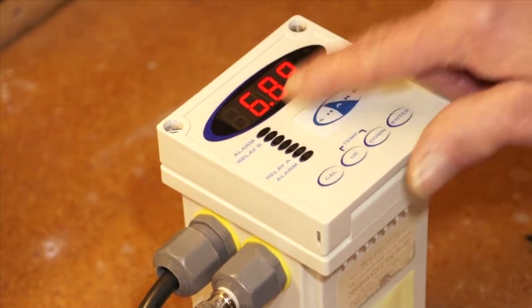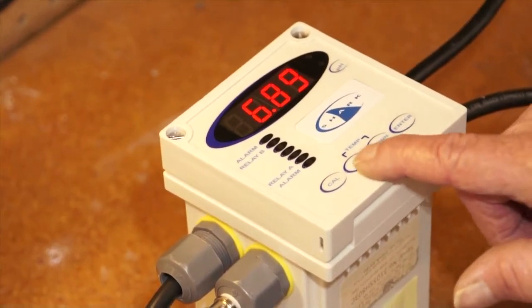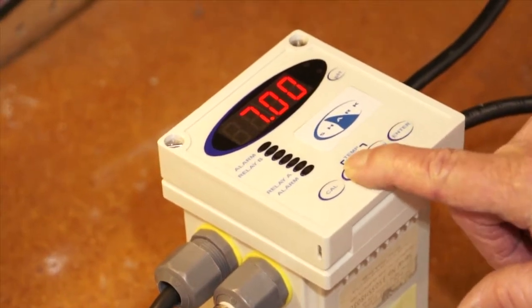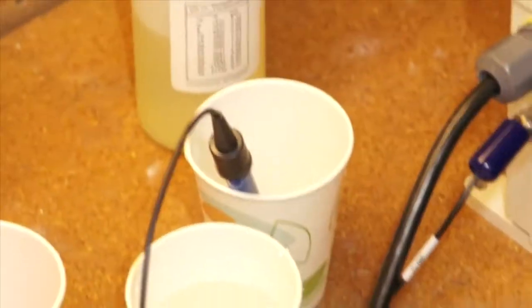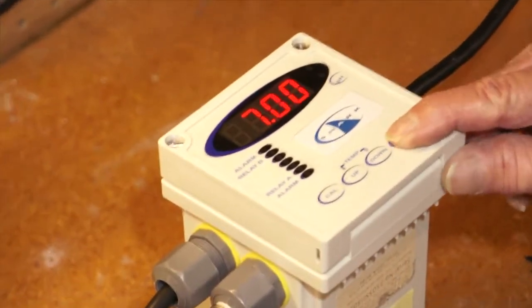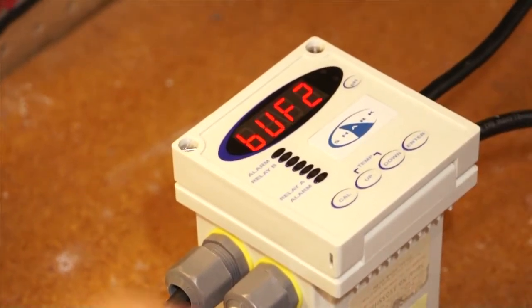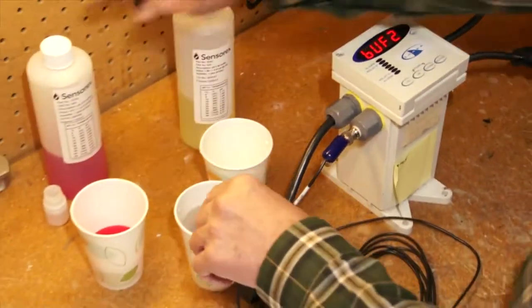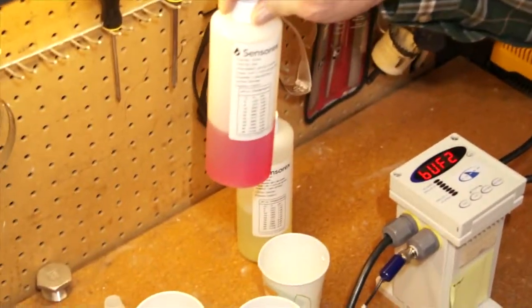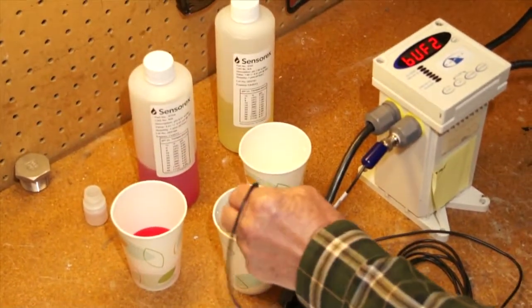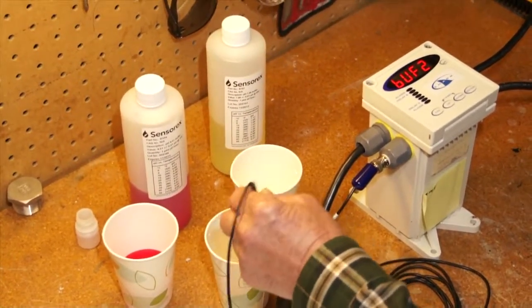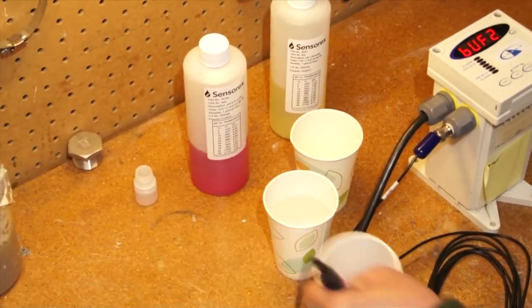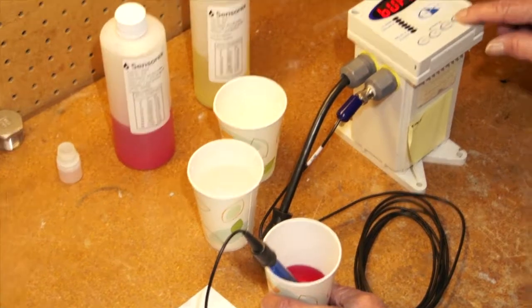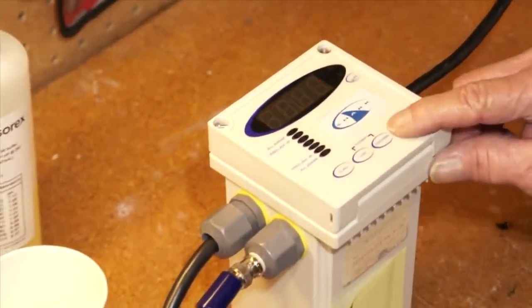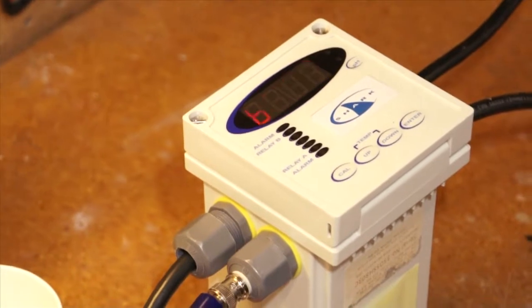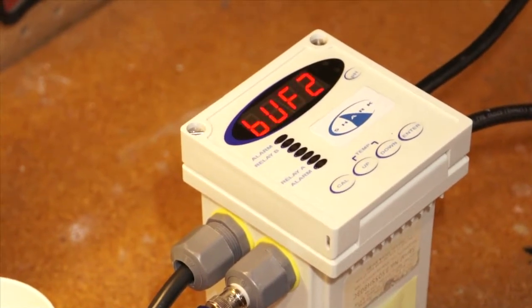Okay, we're off just a smidge. It should be reading 7, so we're going to use the up button to make the reading on the controller match the pH of your buffer solution. When we do that, we hit enter, enter again, and it'll ask for buffer 2. Buffer 2 is the pH 4.01 red material that's furnished with the system. So we're going to rinse the probe. Rinsing is very important if accuracy is very important to you. So we're going to hit enter, enter again, and we'll get a reading in shortly.